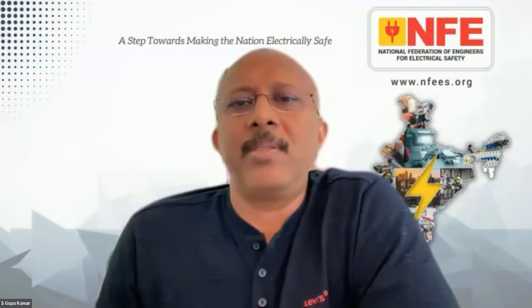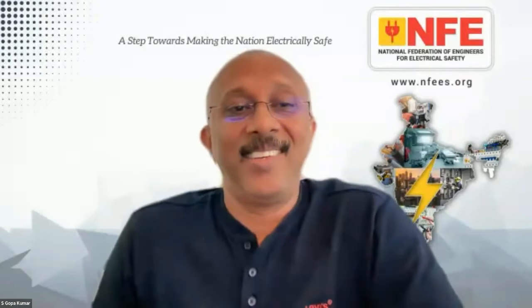And we need to be mindful as well that all electronics now, in their natural performance, will leak to earth. So if you put a clamp meter on an earthing system, you will get natural leakage, and that can be perfectly healthy. It's when you try and disconnect an earth wire and it blows up in your face that you need to be mindful that there could be a problem. Hence, configuration is very important.